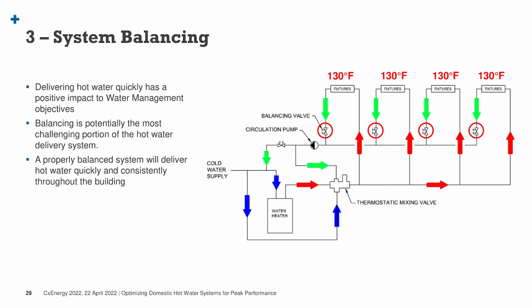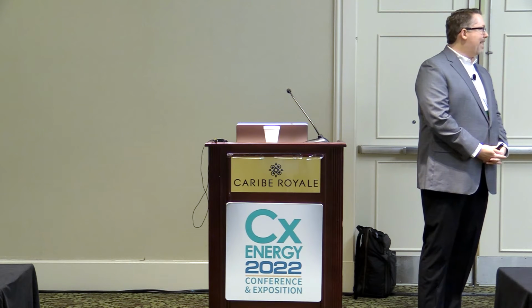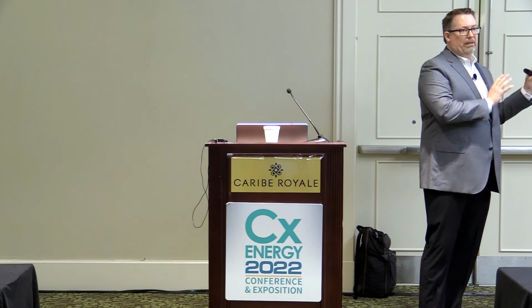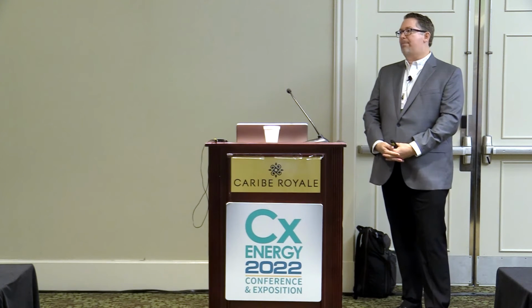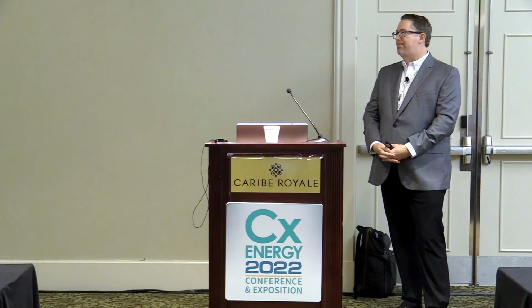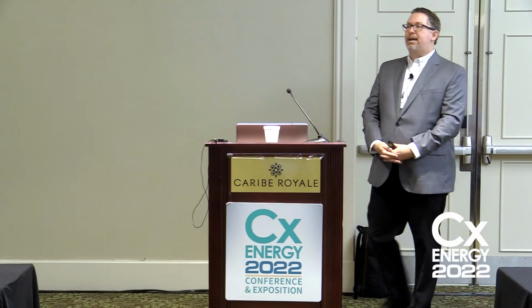This one potentially is the biggest issue, and we really haven't addressed it. When we start looking at technology for water heaters and their efficiency, that has definitely changed over the years, right? They've become more efficient, so they've got higher turn down rates, and we've got condensing water heaters and heat pump water heaters. Digital mixing valves have been out now for several years. Starting to see many manufacturers have that option. That helps to alleviate some of those installation issues or operational issues that mixing valves have had in the past.